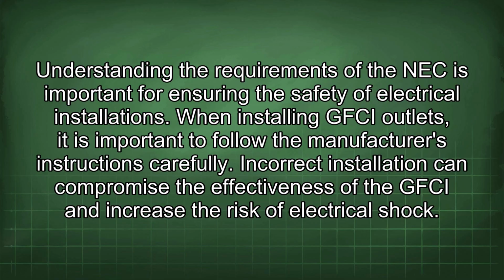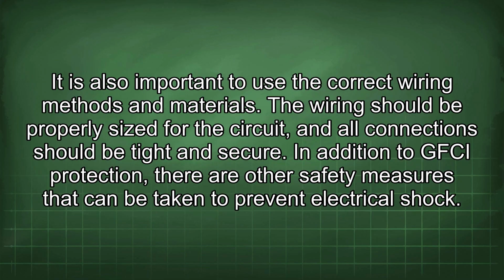When installing GFCI outlets, it is important to follow the manufacturer's instructions carefully. Incorrect installation can compromise the effectiveness of the GFCI and increase the risk of electrical shock. It is also important to use the correct wiring methods and materials. The wiring should be properly sized for the circuit, and all connections should be tight and secure.